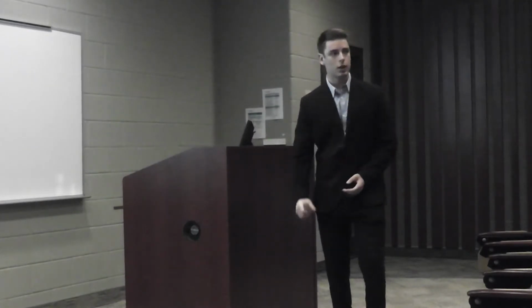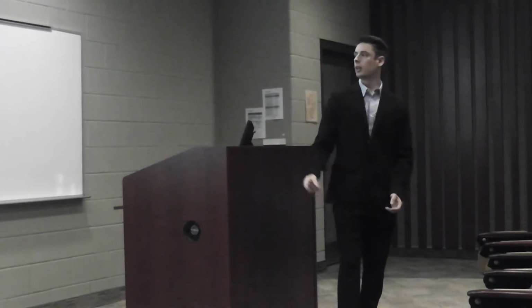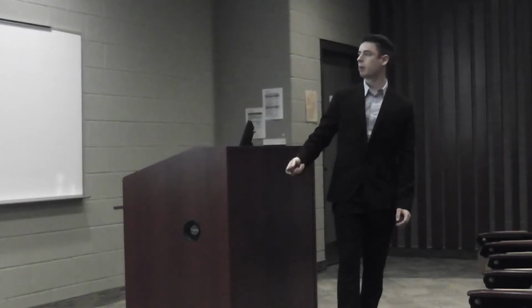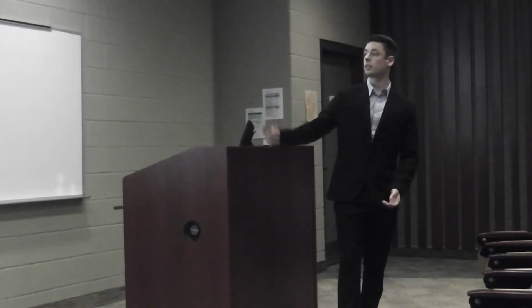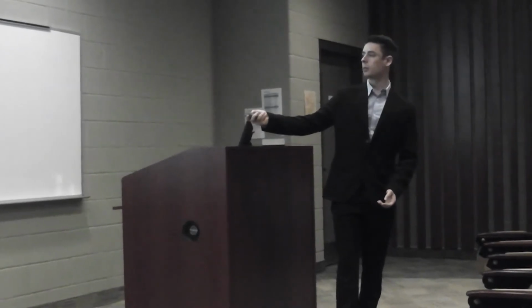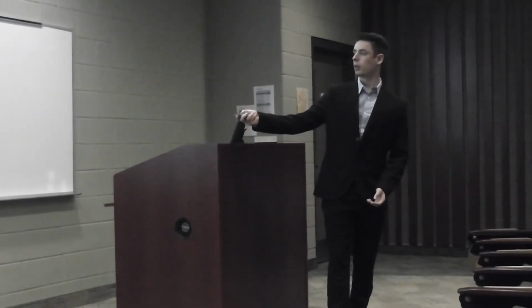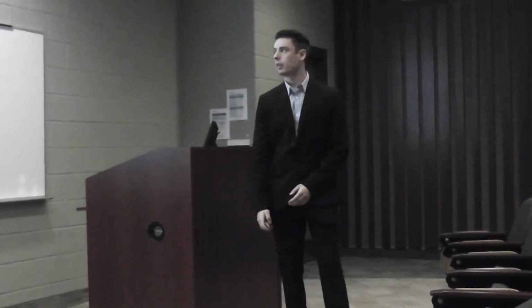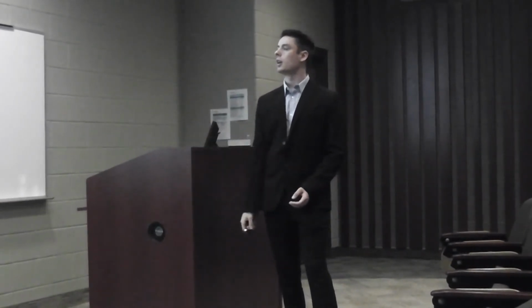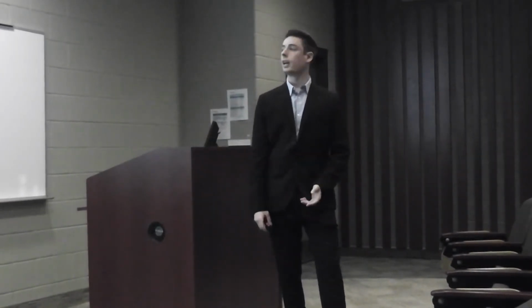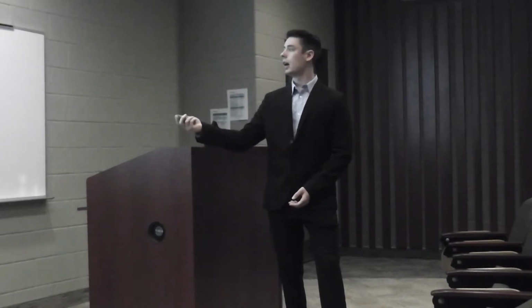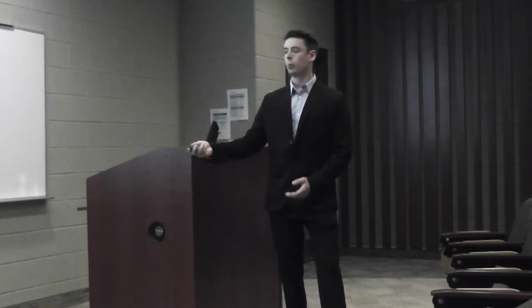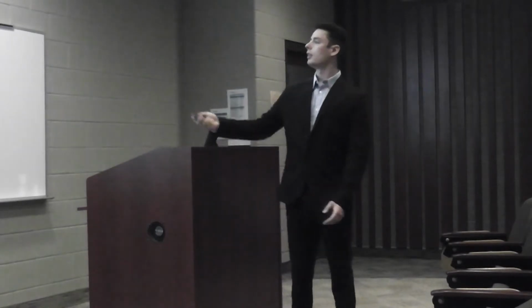So the lighting load, this load doesn't change per hour. There are 16 bulbs at 32 watts, and I'm going to add up all the totals at the end, but this is the formula and that's the total. The occupancy load, these are textbook values for doing light bench work in the area. There are 6 staff, and that's the total BTUs an hour. We'll see all these totals at the end.